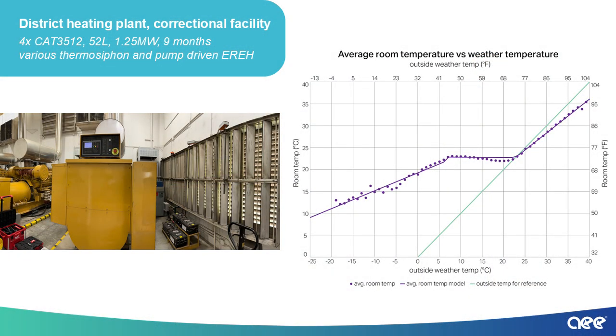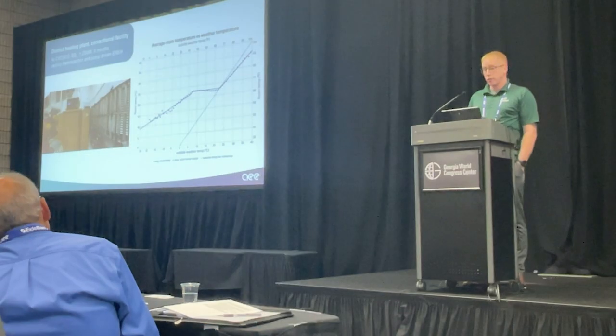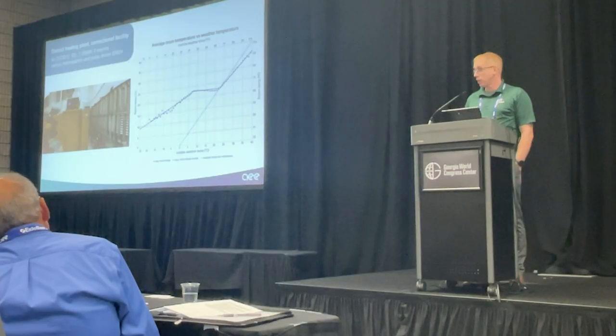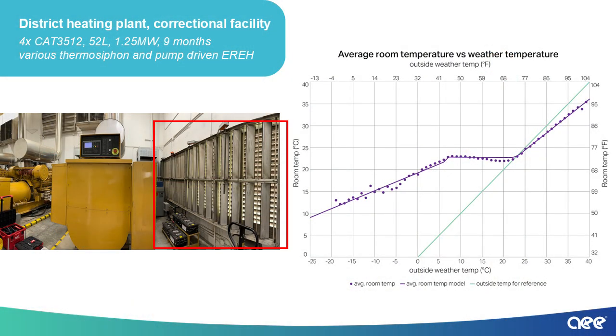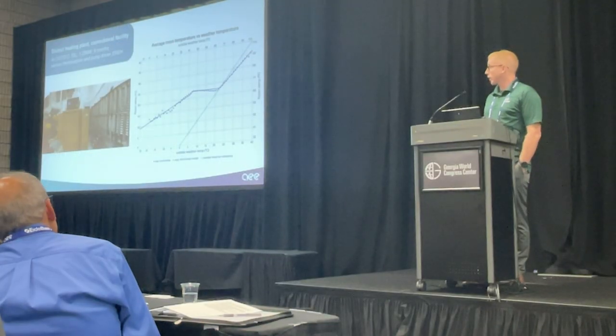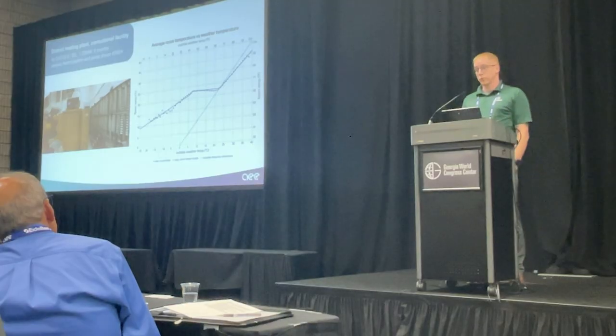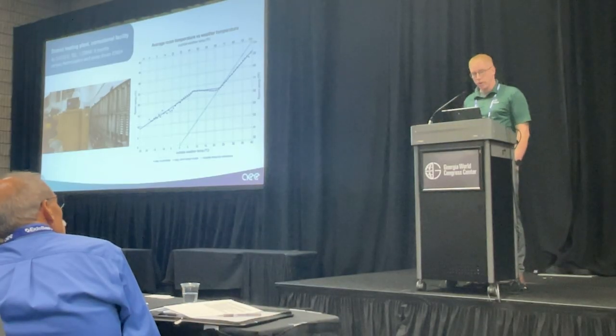The second one I'll look at here is a district heating plant for a correctional facility. In this case, there were 4 slightly smaller gensets within a large room. This room had active cooling when it was above 75 degrees Fahrenheit, which basically meant they opened these louvers here, and fans on the wall above the gensets started. 4-foot diameter fans were pulling air into the room. That obviously affected this engine more than the 3 others to its left, so variation was observed.